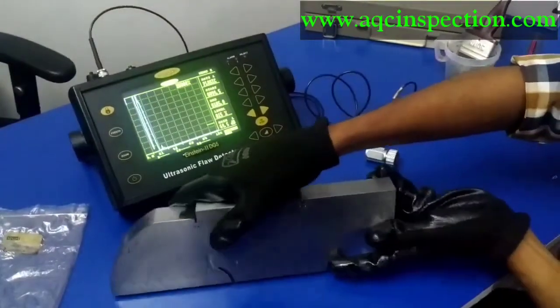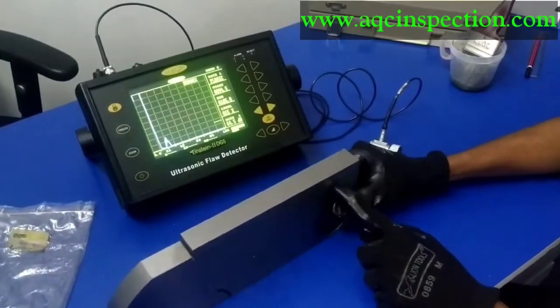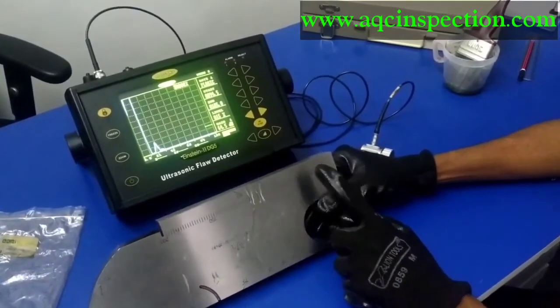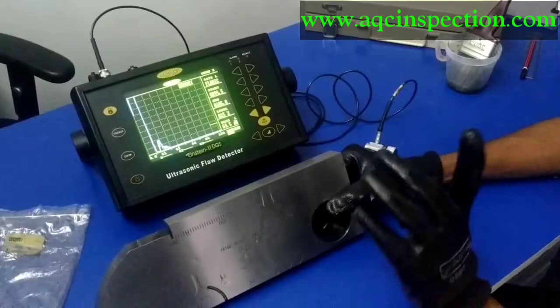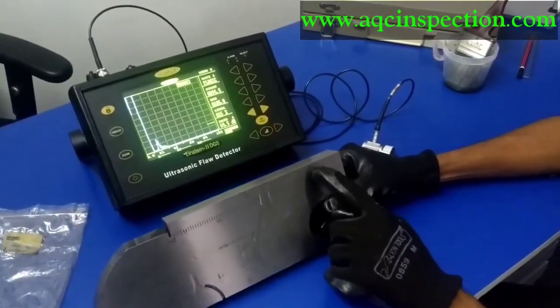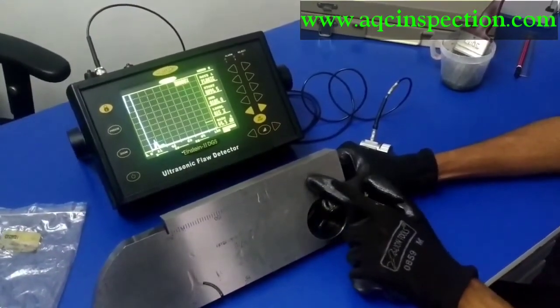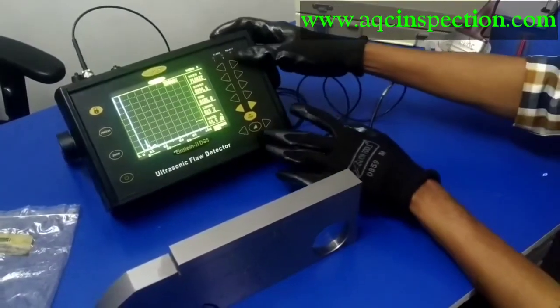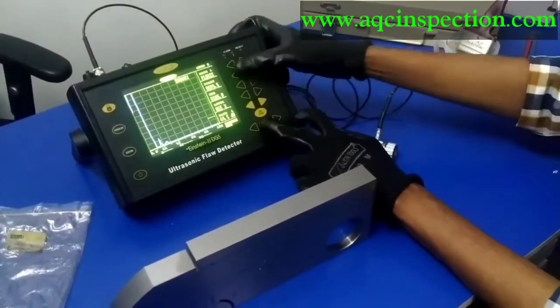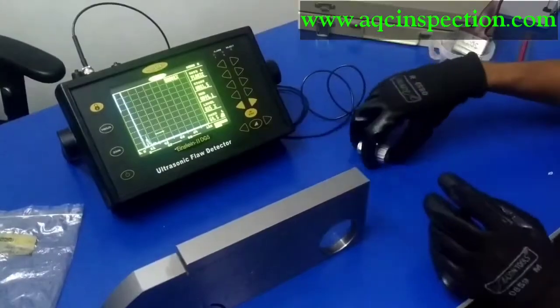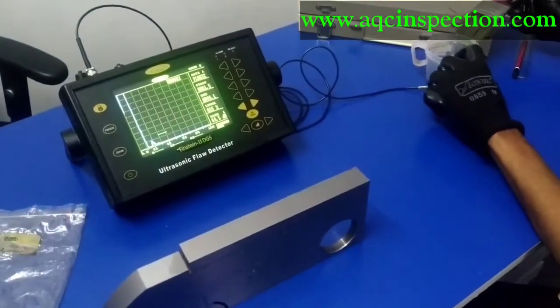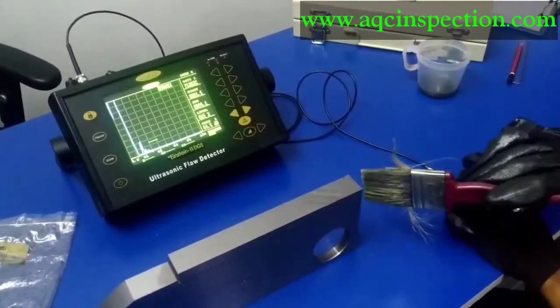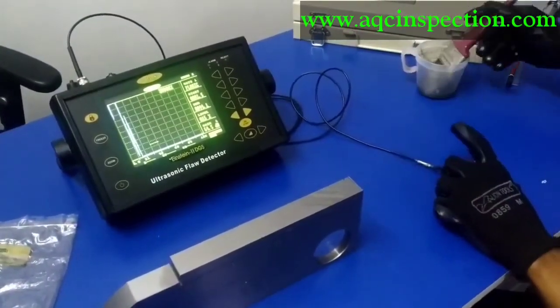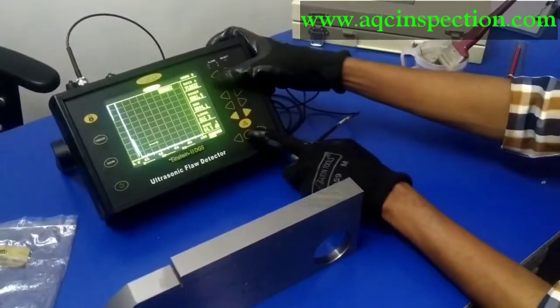Right now I'm going to perform another one, which is called sensitivity calibration, using this side drill hole right here. I have to catch this hole to check whether I'm getting 15 mm from the top, and from here 35 mm. If I'm getting it, then the probe is sensitive enough for calibration for inspection purposes. Okay, I need a little more couplant here and on the side as well. So let me check if I'm going to get a signal right here.